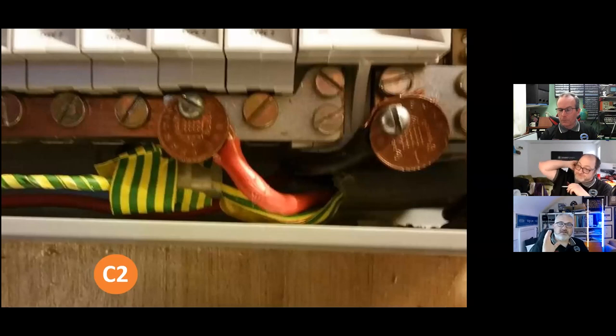But there is, the guys and girls, absolutely, the minute you see that, that's either a danger notification form with a very clear explanation, or it's quoting for a change, because it's not really good enough to leave that there. So I wouldn't argue with a C1. Yeah, Phil's added, the reason is, his personal assessment, C1, is the immediate remedial action. The C2 doesn't require the immediate remedial, and that's why he pushes it to C1, because it pushes him to get rid of the penny washers, and that's why he's thinking C1, which I can't disagree with.